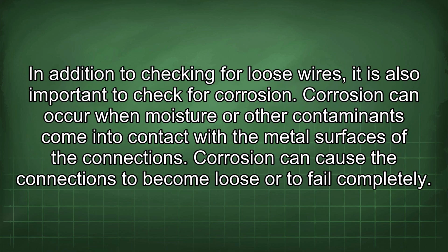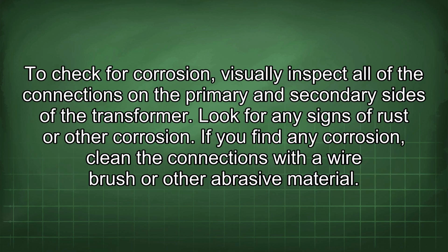In addition to checking for loose wires, it is also important to check for corrosion. Corrosion can occur when moisture or other contaminants come into contact with the metal surfaces of the connections. Corrosion can cause the connections to become loose or to fail completely. To check for corrosion, visually inspect all of the connections on the primary and secondary sides of the transformer. Look for any signs of rust or other corrosion.